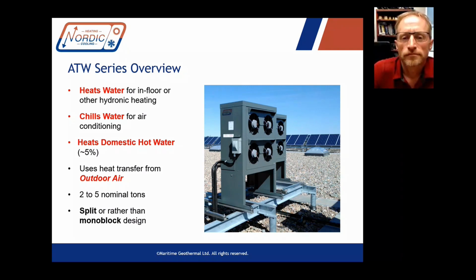In the summertime, we might want to be able to switch it over and do as much preheat as we can, in other words, switch it to heating mode, do as much domestic hot water heating as we can, and then top it up. Yeah, you can do dedicated domestic water preheating just with a heating zone. That would be a tank with a coil in it most of the time, like an indirect tank. What that doesn't have that the desuperheater does is that it's limited to below the main output temperature. So it would heat domestic water on demand, but not right up to 140 degrees Fahrenheit or 60 degrees Celsius. You have a buffer tank for cooling as well, I presume?